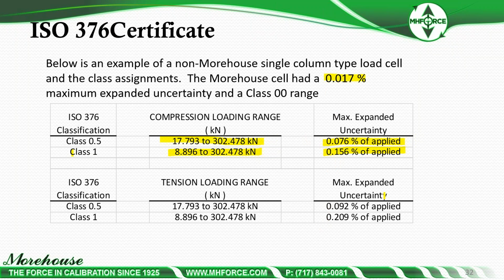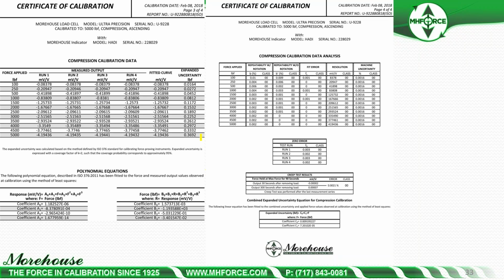versus this up here, the 0.017. So this cell, realistically, is suitable for ISO 7500 calibration. They're probably not going to calibrate many other instruments in accordance with ISO 376 with these types of ranges. Looking at the data in more detail, here's compression calibration data on our CERT, polynomial equations. ISO only allows up to a 3rd degree, so that's all we can use. They may be better at a 5th degree, but it doesn't allow it.